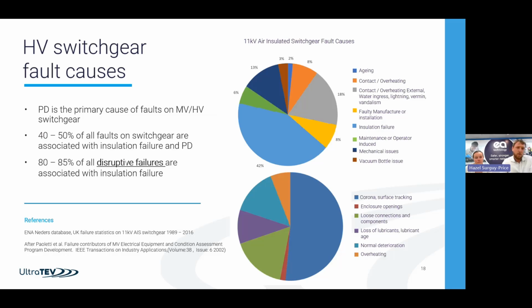So the first step then: what would cause issues on your HV equipment? This is some data for 11 kV air insulated switchgear, from the ENA Neders data. That top graph on the right hand side is saying, look, these are the causes of failure. And by far the biggest section leading to failures is the breakdown of insulation. So if you're going to choose one intervention, you choose to intervene in that area. Insulation breaking down is the bit we're going to look at, and luckily, that's where PD fits in.